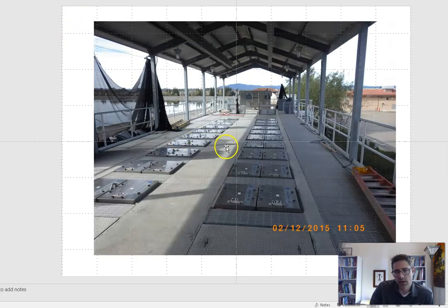This is what a UV system looks like in real life. There's wastewater channels down below this platform, and so the wastewater is flowing down this way. These are access panels where you can open these up, and then a crane, there's a bar up here, a crane goes down on here and can go down and grab the bank of UV lights and pull them up for maintenance and access. So this is really common as far as what a UV system might look like in real life.